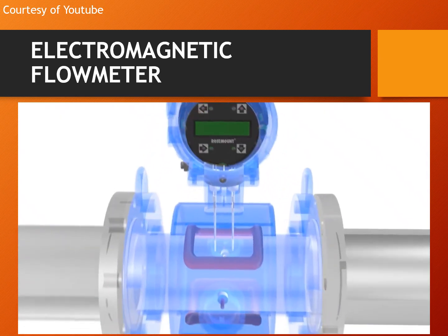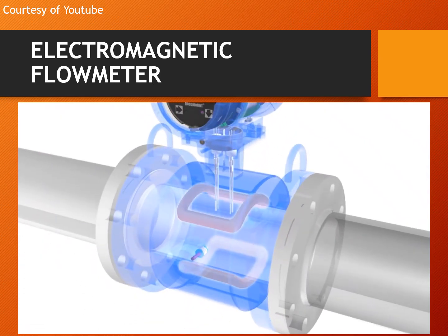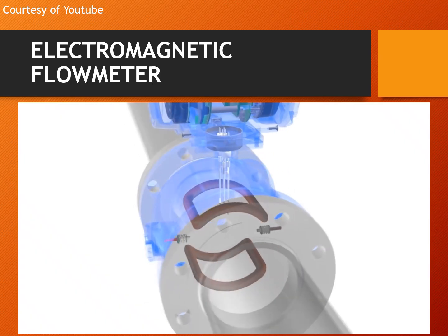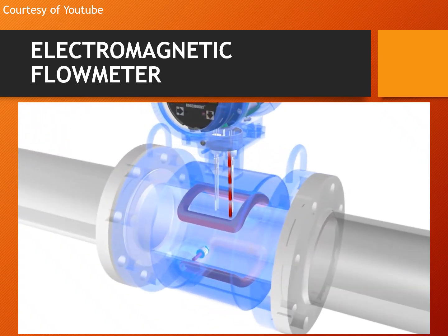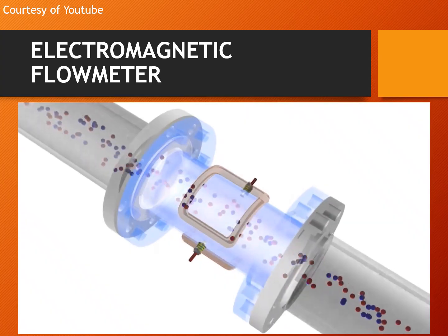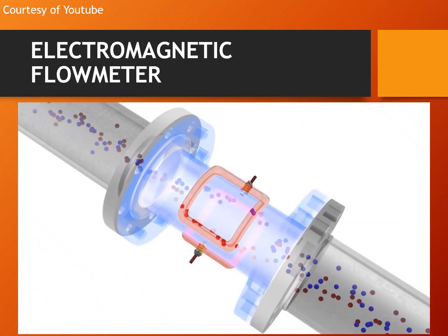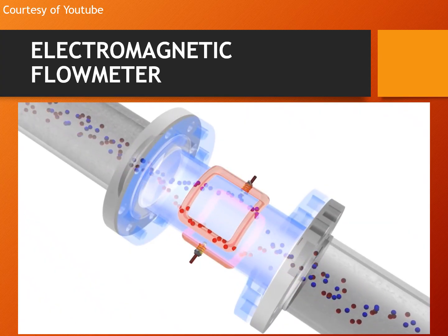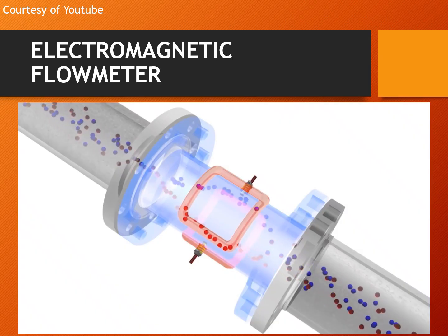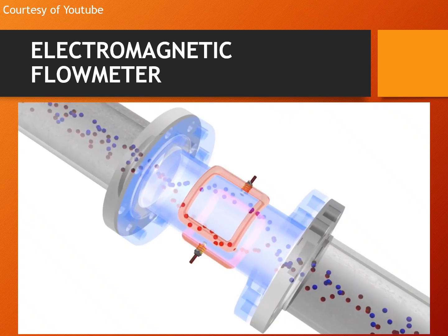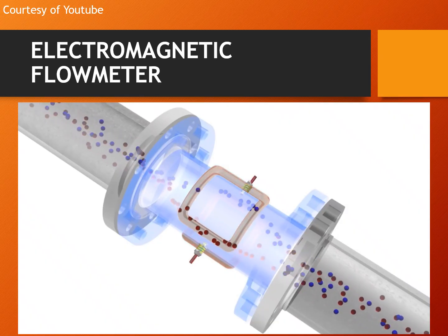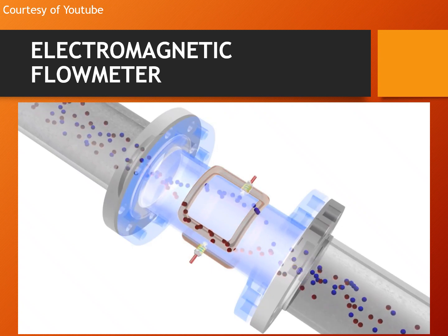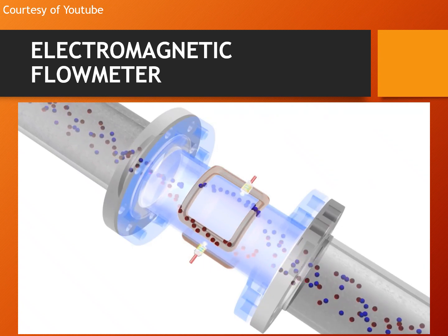To make the flow measurement, the mag meter utilizes a set of coils and a pair of electrodes. The mag meter's coils are driven by the transmitter with an applied current. Once powered, a magnetic field is formed between both coils. Once the pipe is full and the fluid begins to flow, the force of the magnetic field causes the negatively and positively charged particles of the fluid to separate as they pass through the magnetic field. This separation causes an induced voltage to be formed between the electrodes and the sensor.